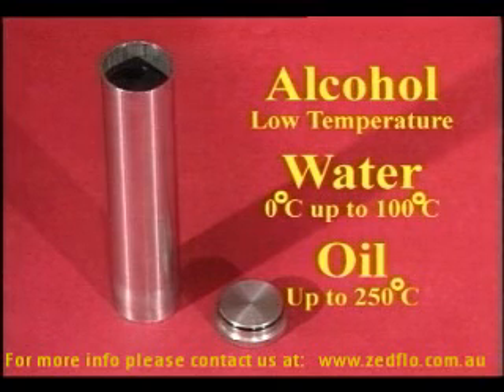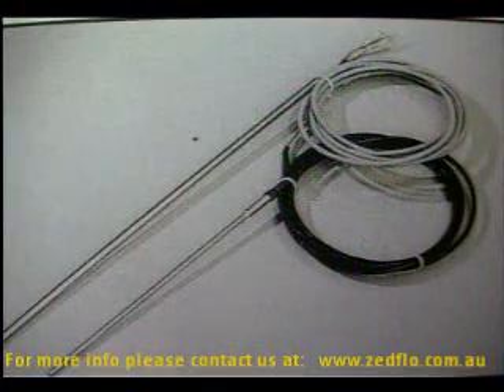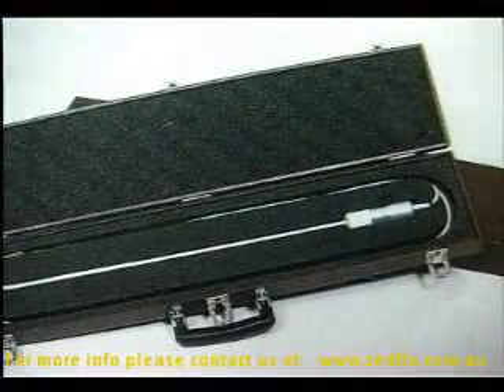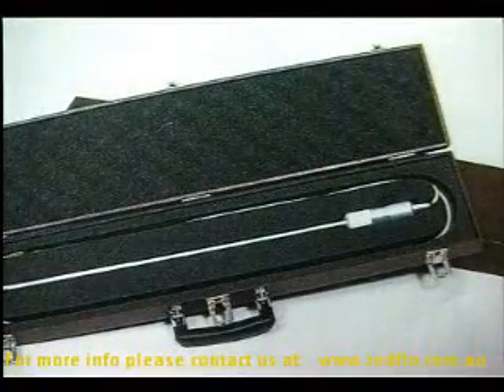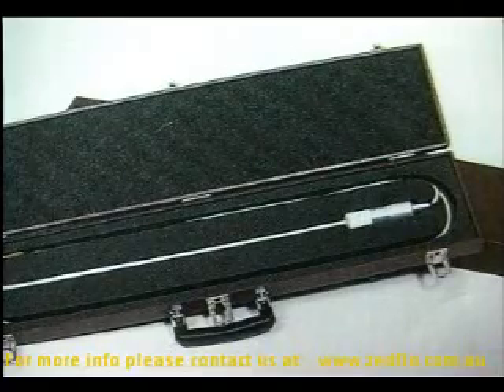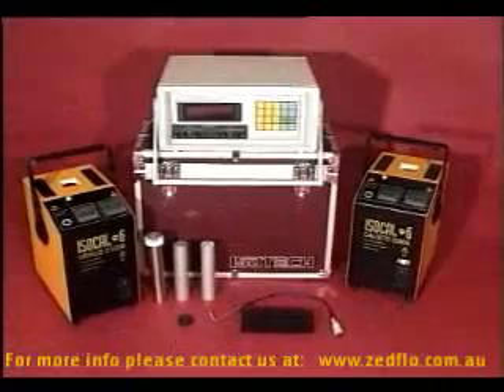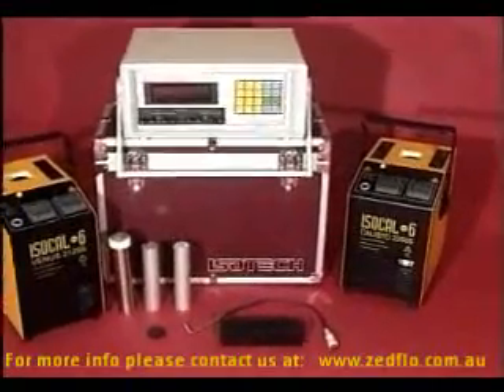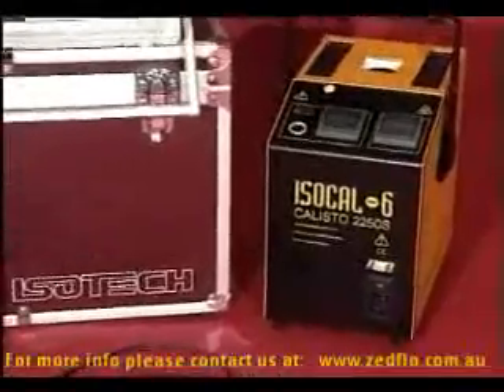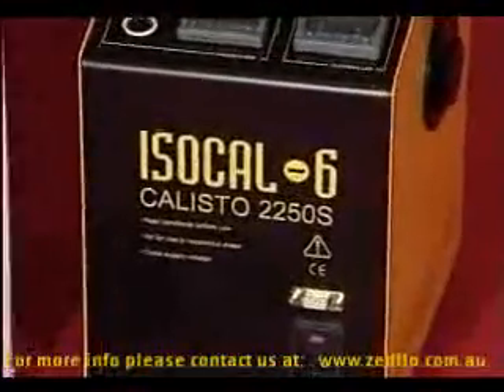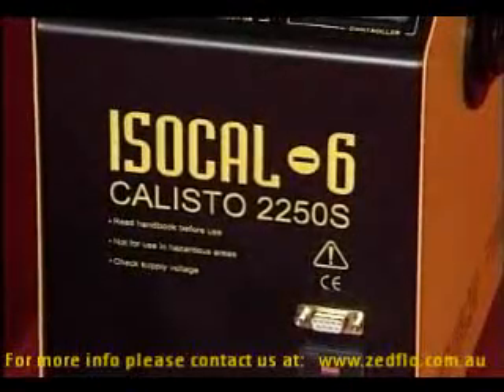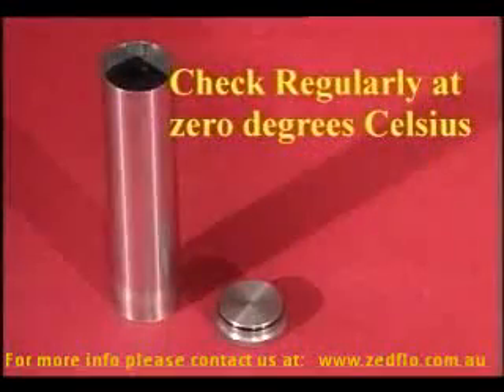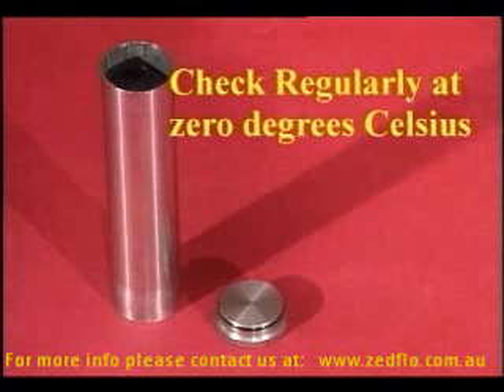But that's not all this little liquid bath will do. If you have a calibrated working standard as a reference, it's your job to relate all the sensors you're calibrating to that calibrated standard. But what happens if that calibrated standard is drifting, changing its characteristics? Then all the results relating back to that are in error. As a calibration facility, you must be able to recheck your standard thermometer, and to ensure that your reference thermometer hasn't shifted. The common way to do that is to check the value at 0 degrees Celsius regularly, and if the sensor hasn't changed, then you have no need to recalibrate it. This will actually save you money.